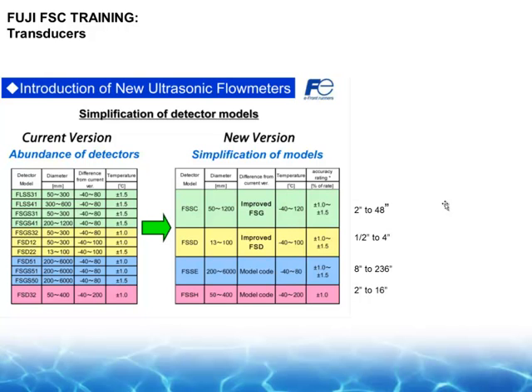Here's the changeroos. Here's the transducers. Fuji's largest fault is they change their transducer part numbers like I change my shirt, and the GUI interface is not always up to date, so people make their inquiries all the time. They usually use the same prefaces, the last two digits there. But what they've done now is they have compiled the 31 and the 41 sensors there into the FSSC, which will work. It's a 1 megahertz transducer with a different crystal angle, which has enhanced its performance even more.